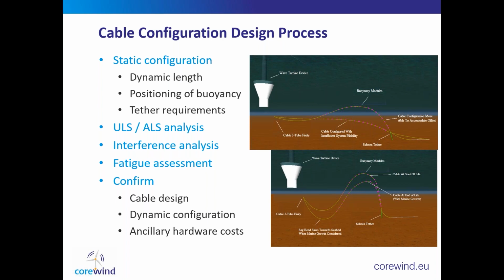We do extreme and accidental limit state analysis, as well as interference with adjacent lines and mooring lines, to ensure that the tensile and bending limits of the cable are not violated. Fatigue analysis over lifetime to ensure that there is adequate design resilience of the cable components. And we base this on best practice and experience from oil and gas and other floating offshore wind projects. And this then can confirm the cable design, the dynamic configuration, and the ancillary hardware costs associated.